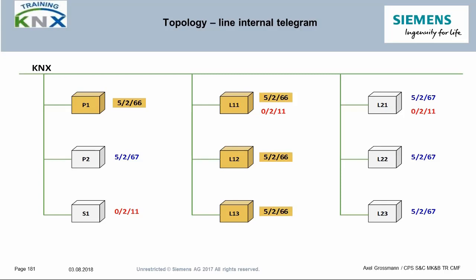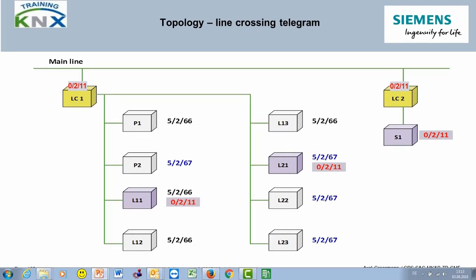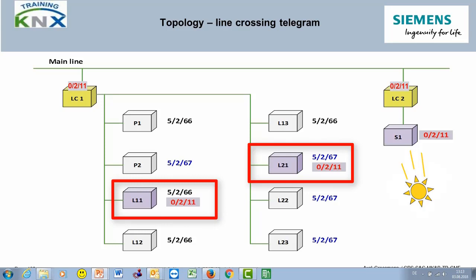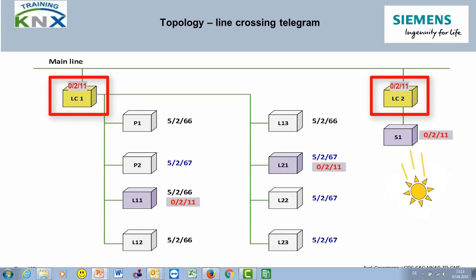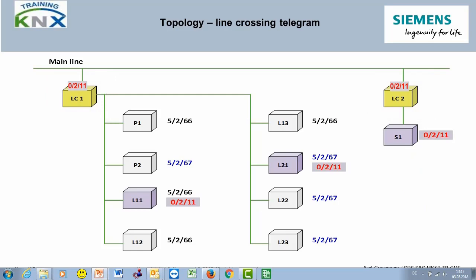This picture shows the internal communication within the line segment. It is only important to note that the corresponding push buttons and actuator channels are connected to the same group addresses. Now looking at the same function across three lines: the light sensor S1 is now on subline 2, while the push button and actuators continue to be on subline 1. The luminaires L11 and L21 are controlled by this light sensor. Therefore, the corresponding group address 0211 must be entered in the filter table of both couplers.